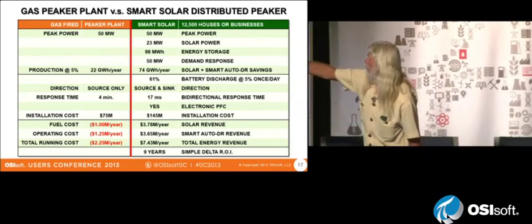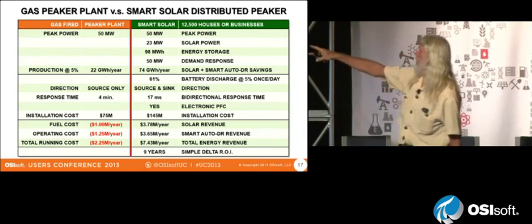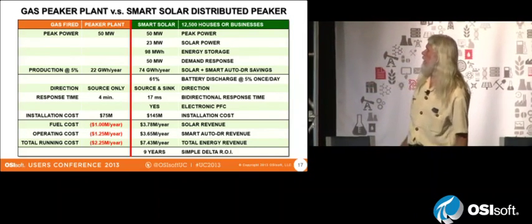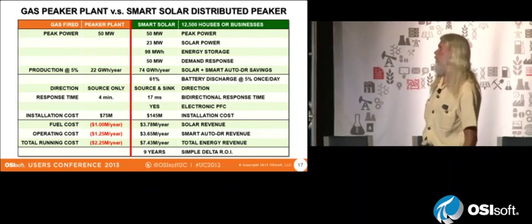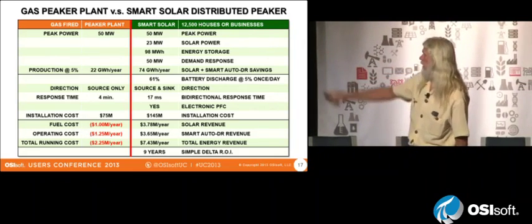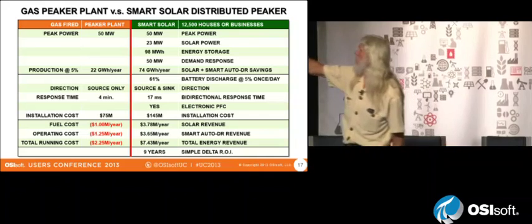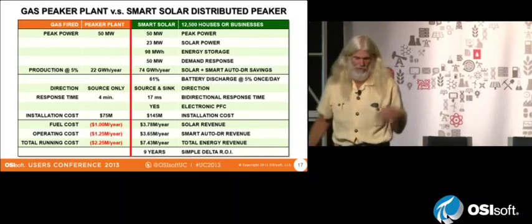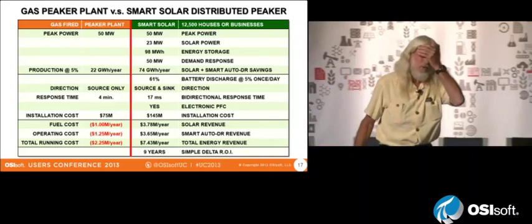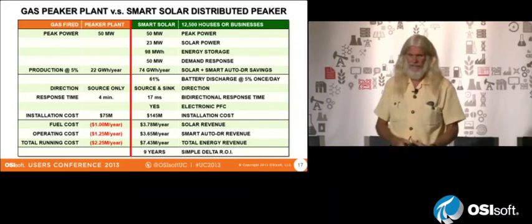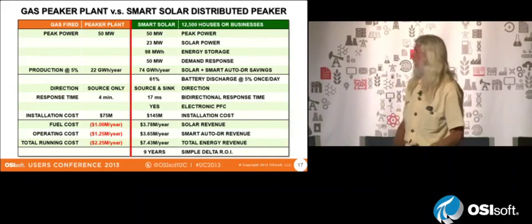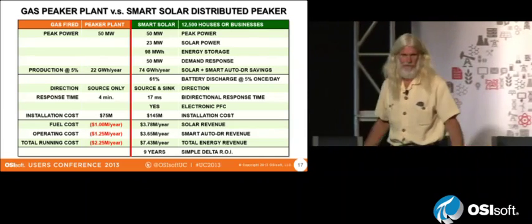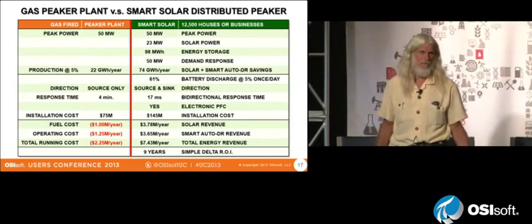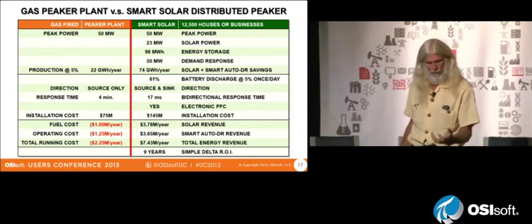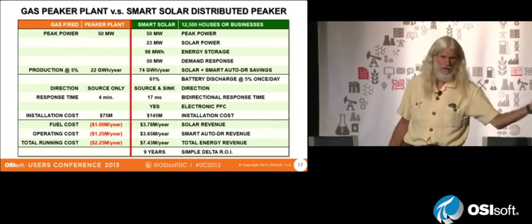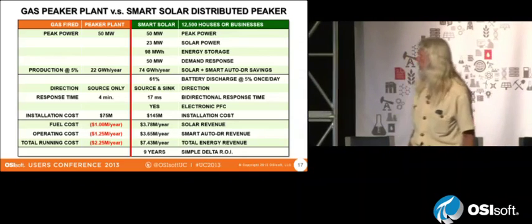So the actual amount of electricity it's producing is significant. Peaker plants average 1 to 10% utilization, so I just picked 5%. If you do 5% once a day, you're going to discharge your batteries by 61%, but that's if you only do it once a day. Real use patterns will be spread out over several times: twice a day, it'd be 30%; four times a day, only 15%. So you're getting into the area where your batteries will basically last a really long time, and it's a really economical use of the batteries.